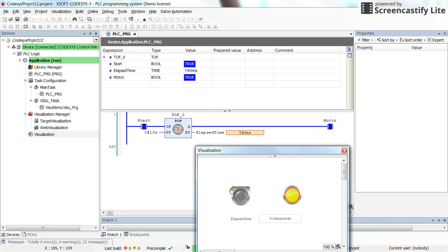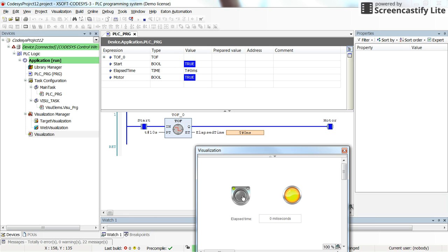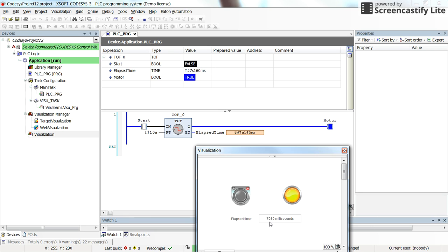Whenever I turn off the input, so the start goes from true to false, the timer will be actuated and it will take 10 seconds for the output of the timer to turn off. As you already know from the previous video. And here we see the elapsed time in terms of milliseconds. It will go up to 10 seconds or 10,000 milliseconds and then the motor will be turned off.